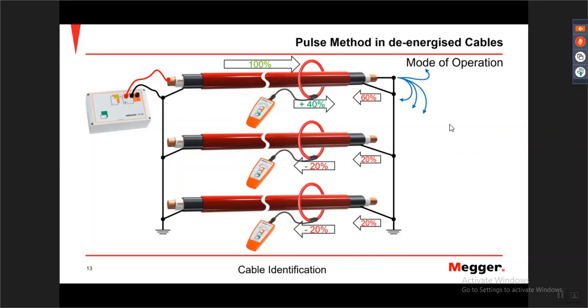You will get a 40% difference between the cores, and this will show that you have a signal. So you have a positive signal on the core connected to the generator, shown by green LEDs. The other two cores will show a red signal, which shows the negative flow.